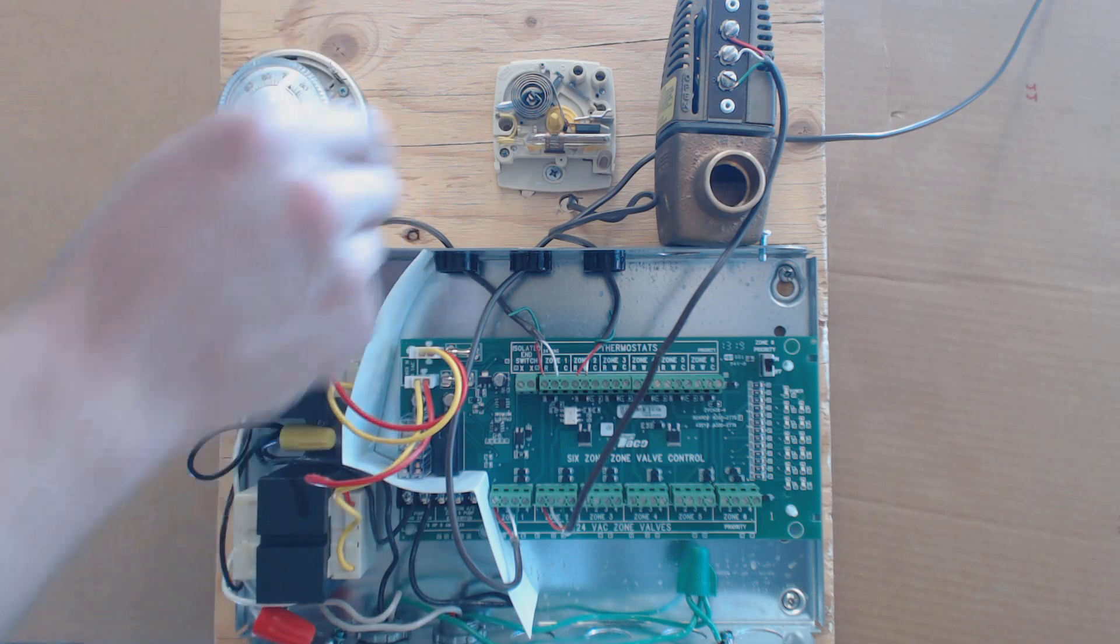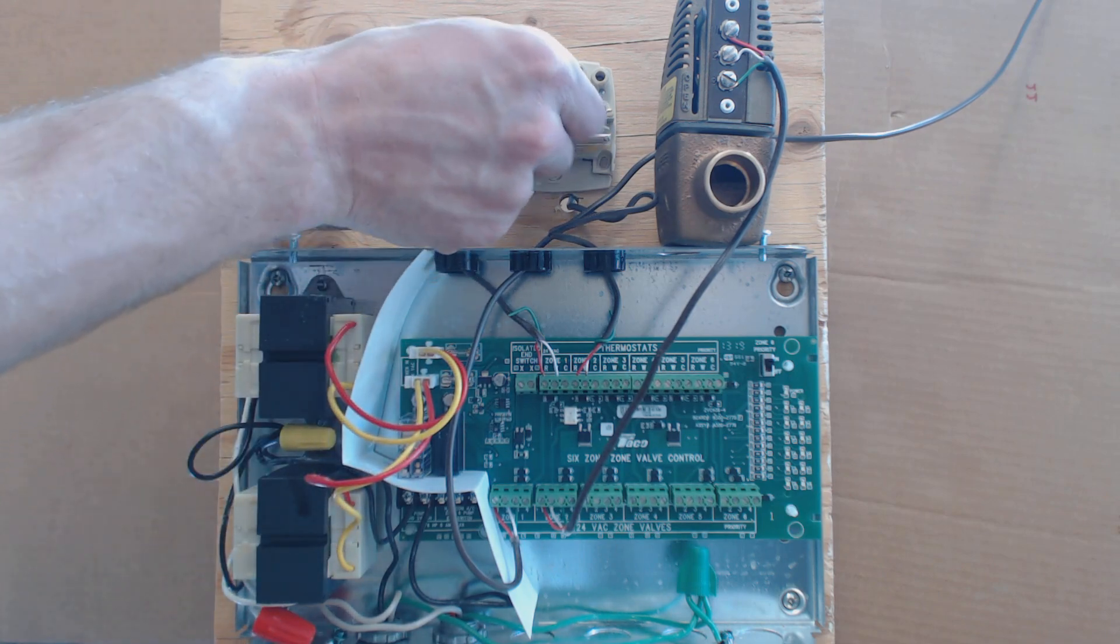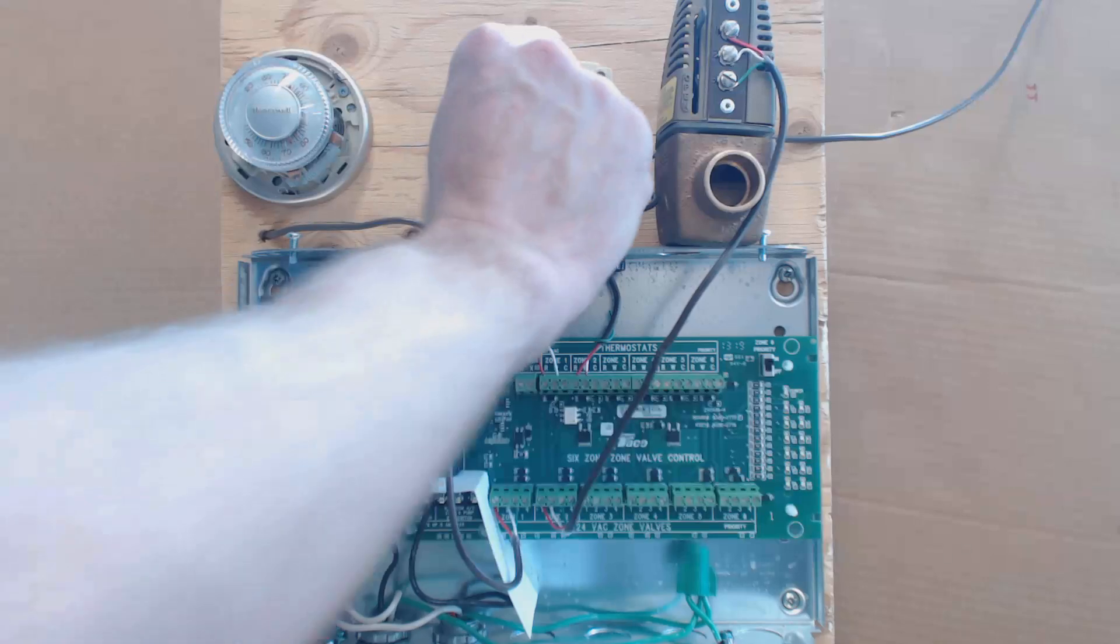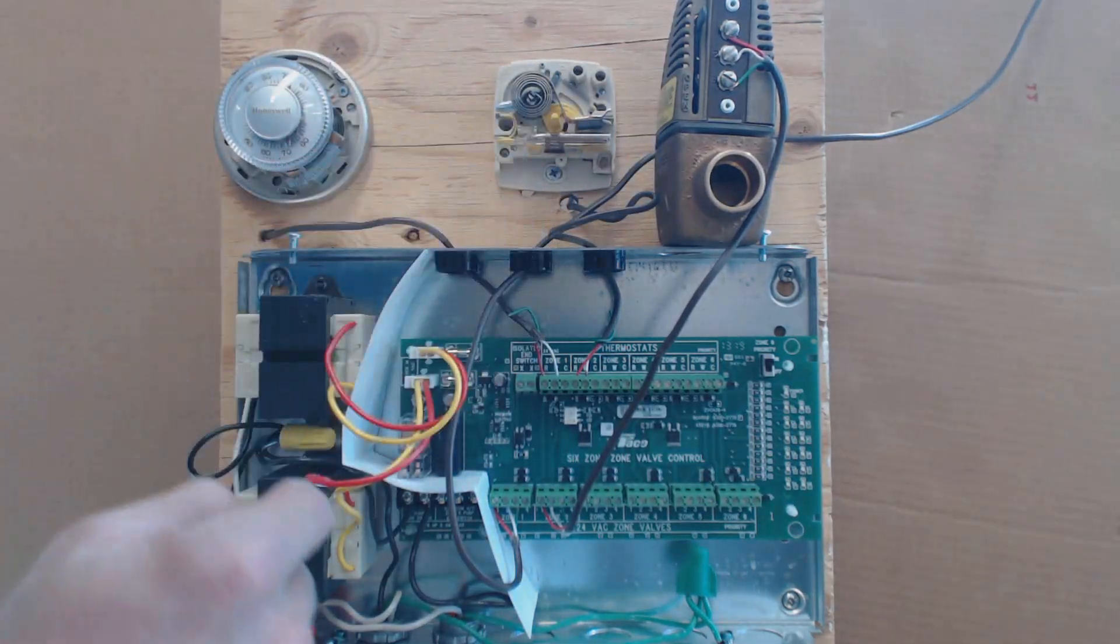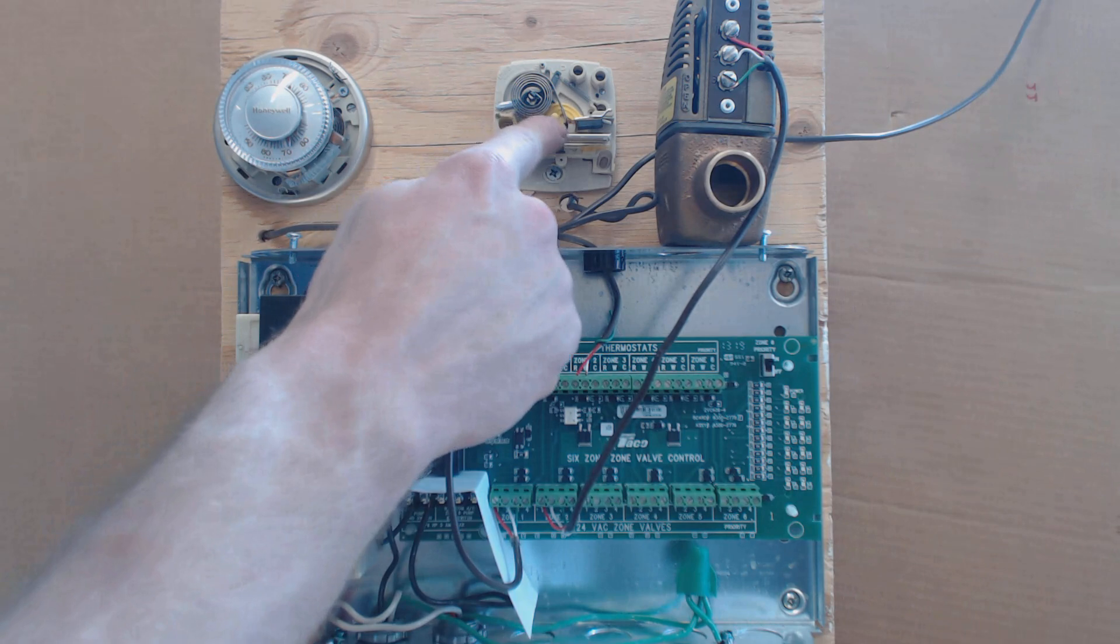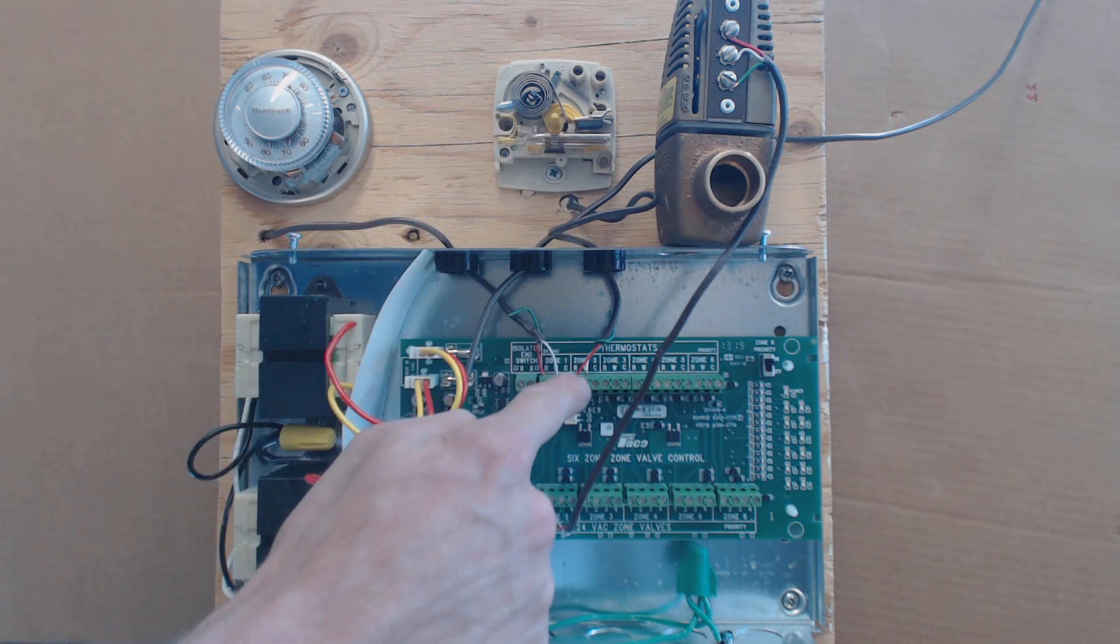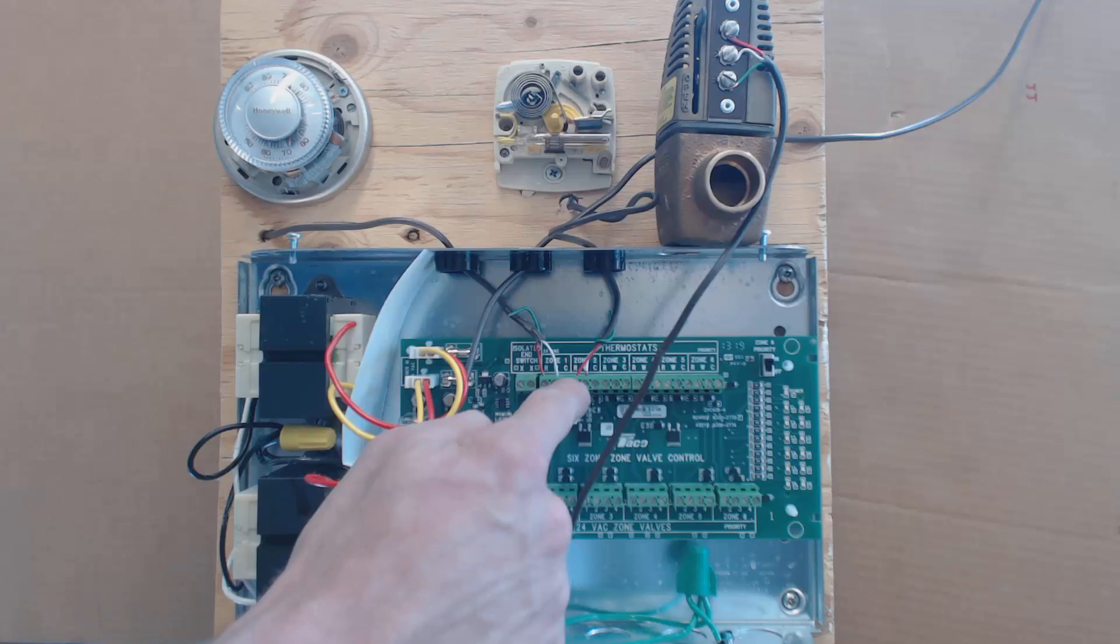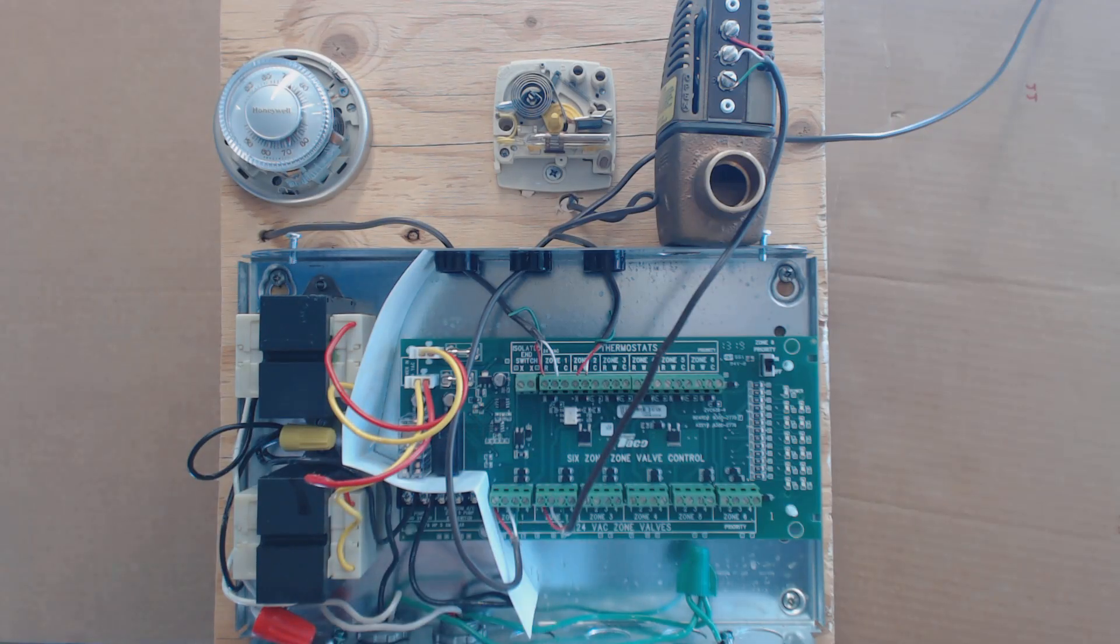Then when you call for heat, these two are going to touch. Now they're touching on this particular thermostat. Now the R and W are touching in this thermostat. W is coming back down as the power wire. It's a signal wire to the control board telling the zone valve to turn on.